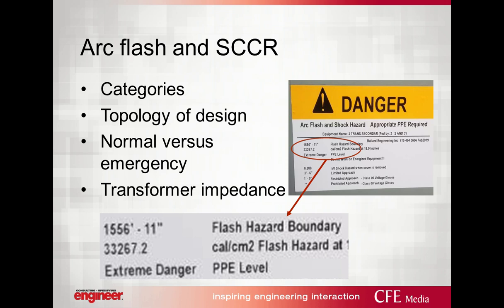Thanks. So one of the things that's changed throughout the decades is the topology of our design. The way that we design systems for selective coordination and managing arc flash and the SCCR has changed the way that we're doing things. We used to have a lot of sub-distribution panels. We're not doing that anymore. Now we're trying to make sure that we comply with selective coordination, but that's also having a side effect on the amount of arc flash energy that we're going to have available.